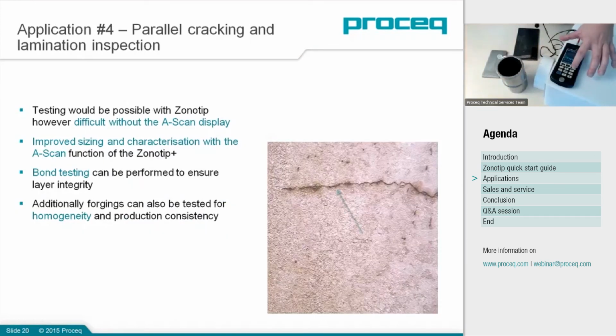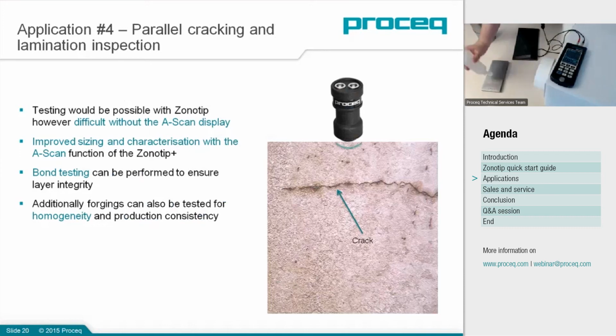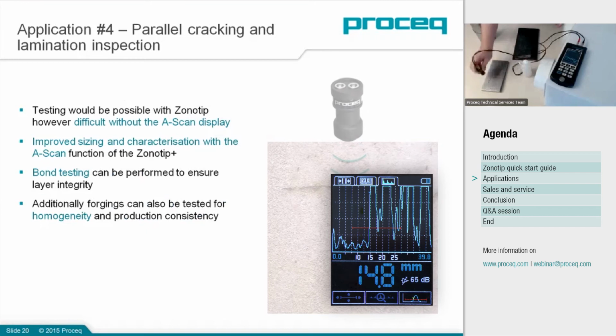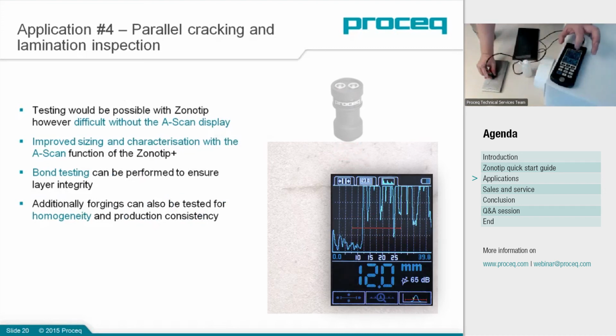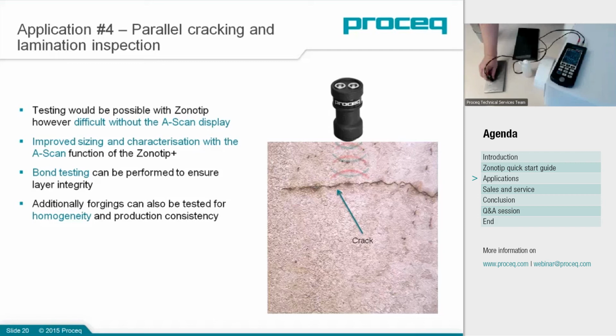Okay, next application we've got for you is detecting possible cracks and flaws. Move this out of the way. I've got a plate here which has a pre-manufactured delamination in it, for example. So what you get is your normal thickness reading of the plate, and you can scan along, and as you get to a delamination, you can see there, we're scanning over the delamination now, it's giving a reading of 12. The normal thickness of the plate is 14.8, but as we move over the delamination, we get a reading of 12. So that means we've got a defect. Let's see if I can find that again. There we go. It's over there. So that means we've got a delamination 3 millimeters away from the back wall surface. And you can use the A-scan, we don't have so much time here, to really characterise and size that defect if you bring the gain down, for example.